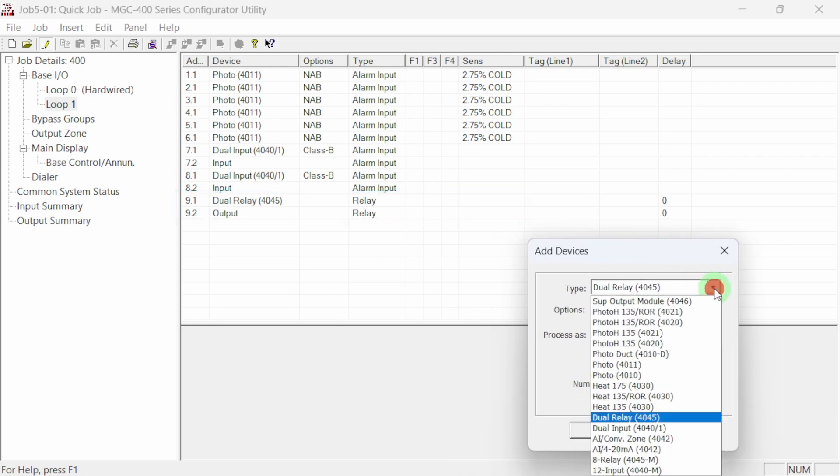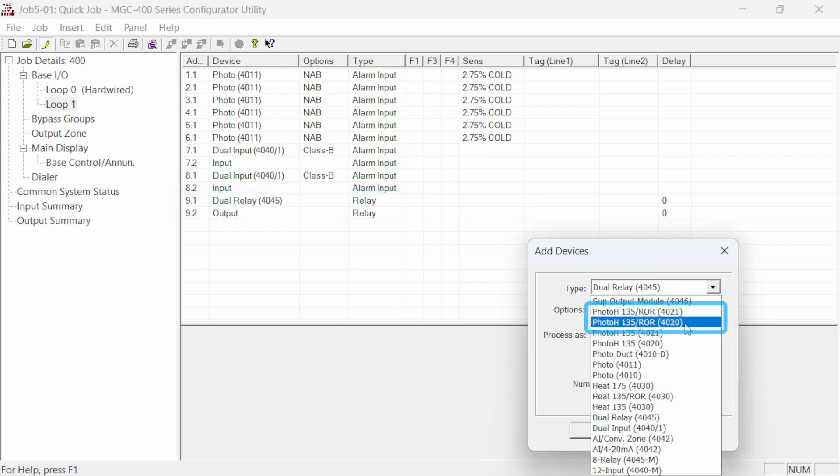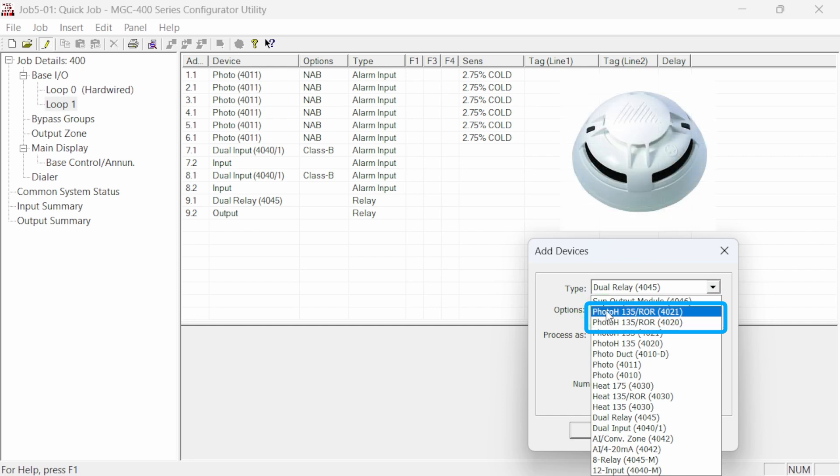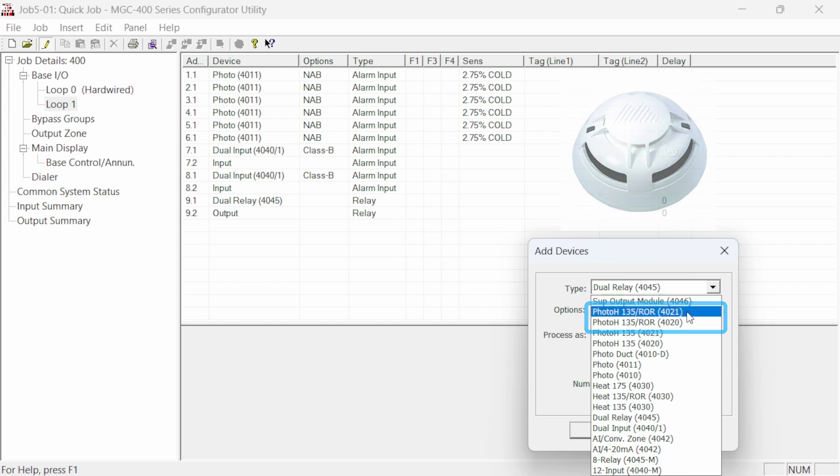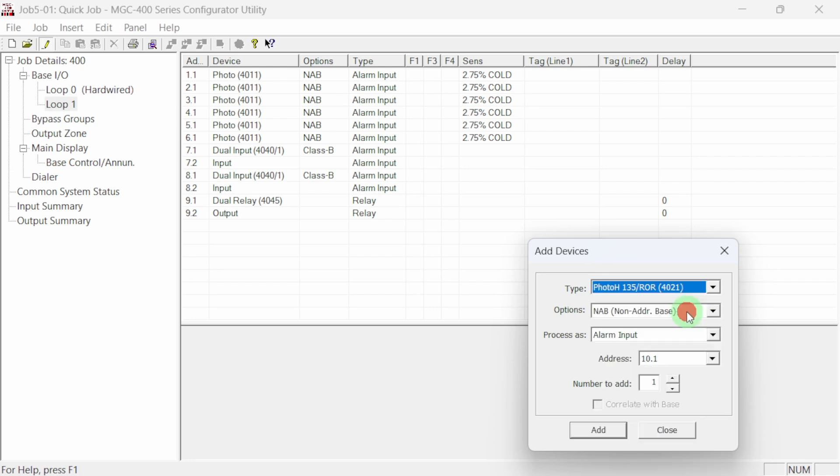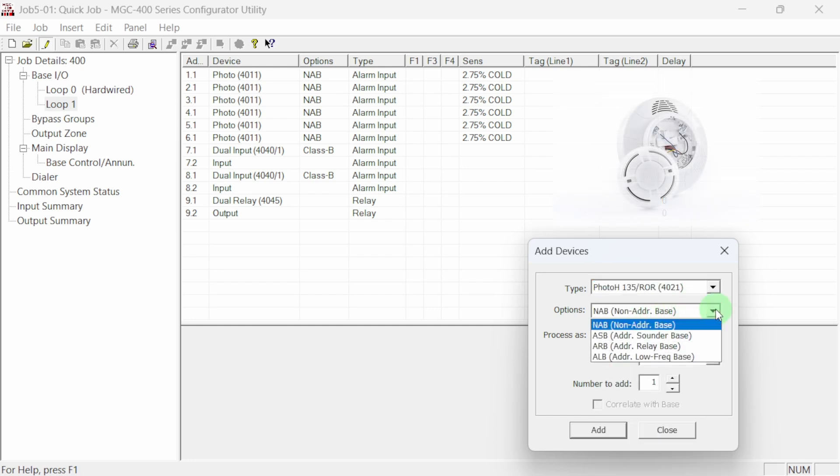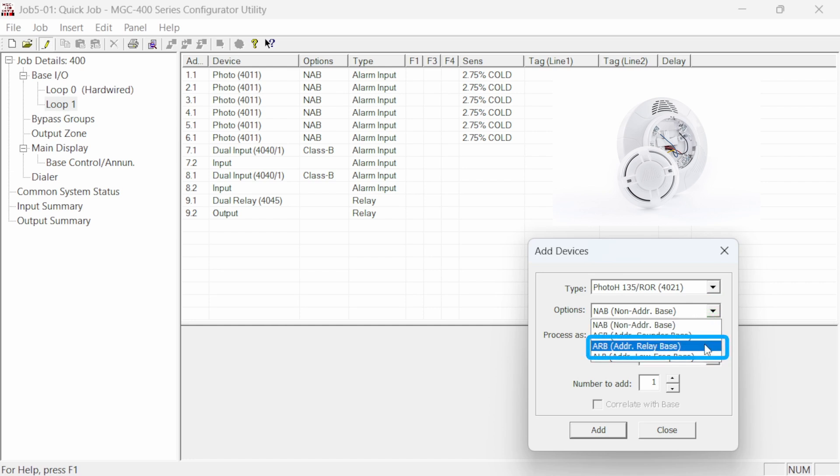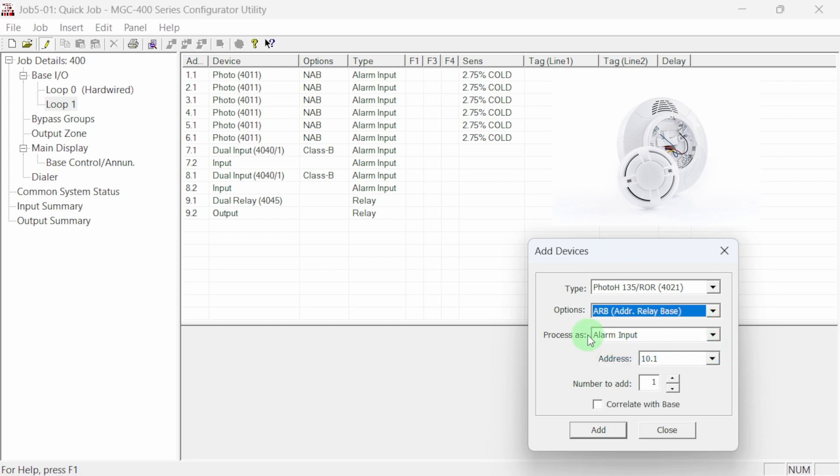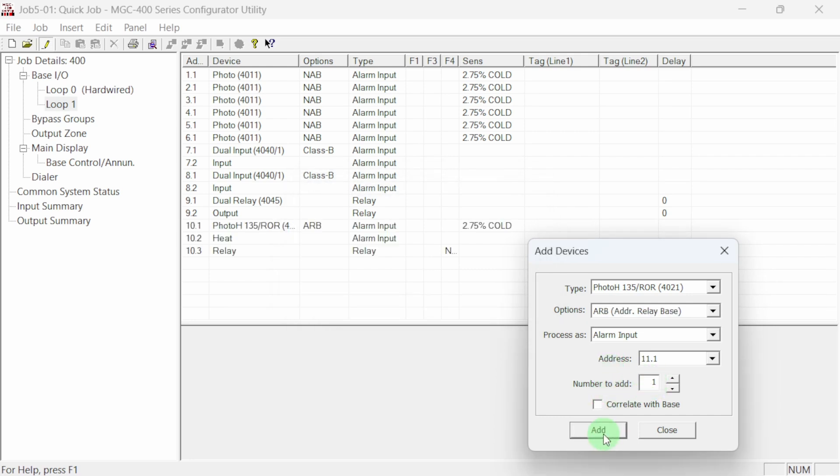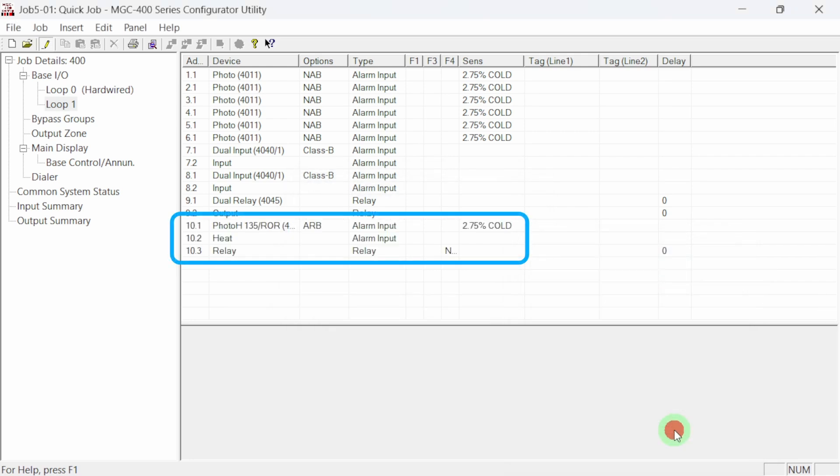For our last example, let's add a dual sensor photoelectric smoke with a 135 degree rate of rise heat sensor. We'll choose the newer 4021 sensor. Be sure to select the proper model to match your actual devices. For this dual sensor head, we'll choose an addressable relay base for installation. This will give us a programmable relay located in the base of this device. We can leave the quantity set to one and click on add and then close the dialog box.